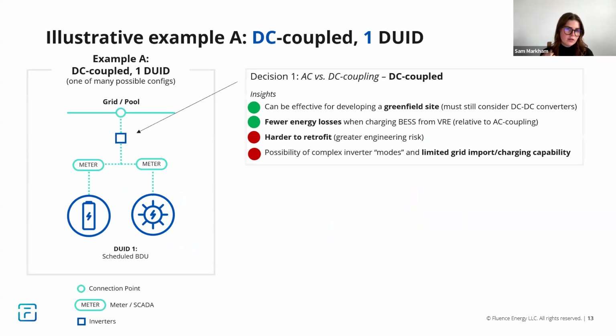So jumping over to the first one, this is DC coupled, meaning there's multiple assets located behind the same inverter. This can be effective for developing a greenfield site, although you have to consider DC to DC converters. It's likely to experience fewer energy losses when charging the BESS directly from the solar plant relative to AC coupling. However, drawbacks are it can be harder to retrofit and comes with greater engineering risk if adding a battery to an existing solar plant, plus possibility of complex inverter modes and limited grid import/charging capability at certain times.